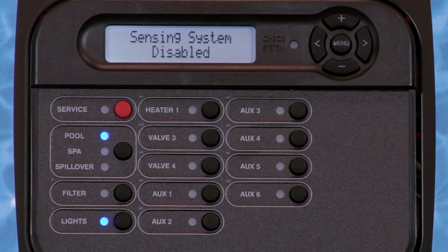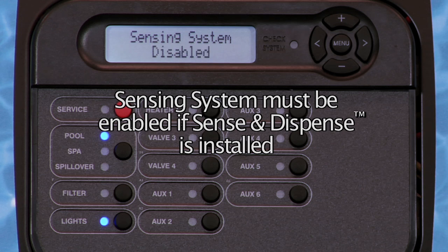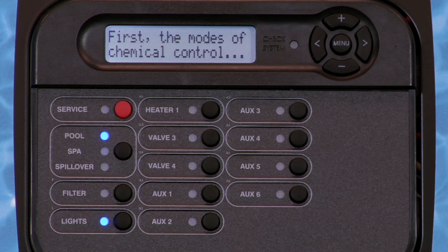The display reads, Sensing System Disabled. If Sense and Dispense is installed, this must be enabled by pressing the plus or minus key. Press the right arrow key to move to the next screen in the chemistry wizard. The display will read, First, the modes of chemical control. At this point, you are guided through the rest of the chemistry configuration menu by pressing the right arrow key.